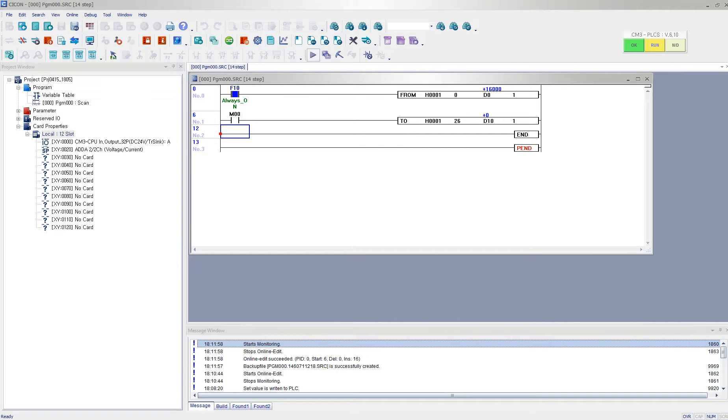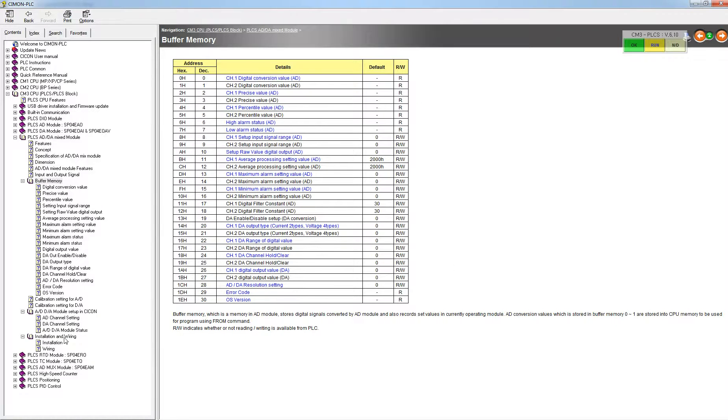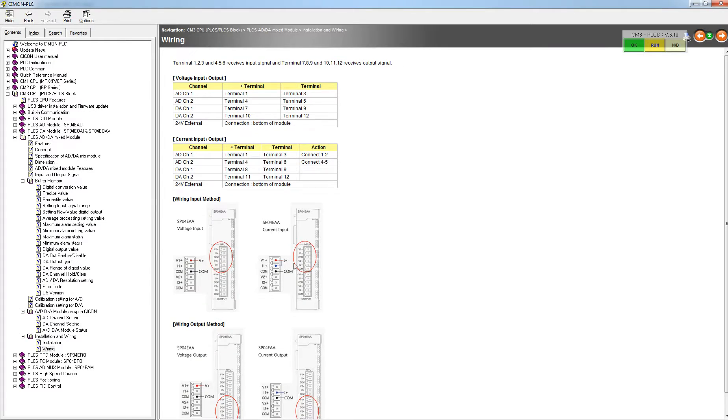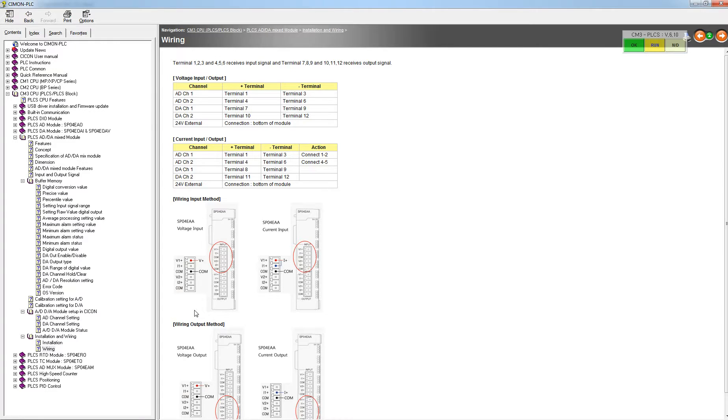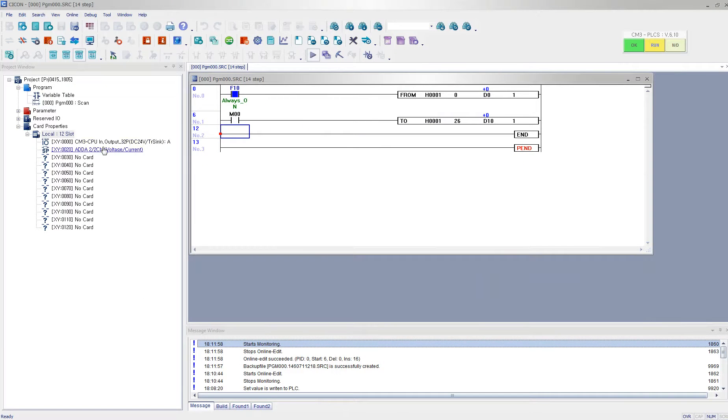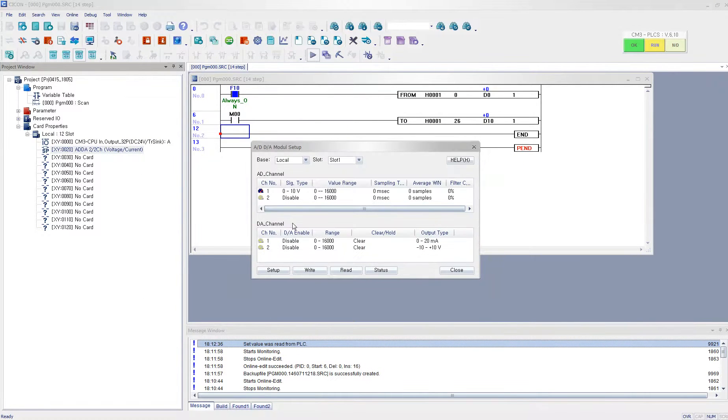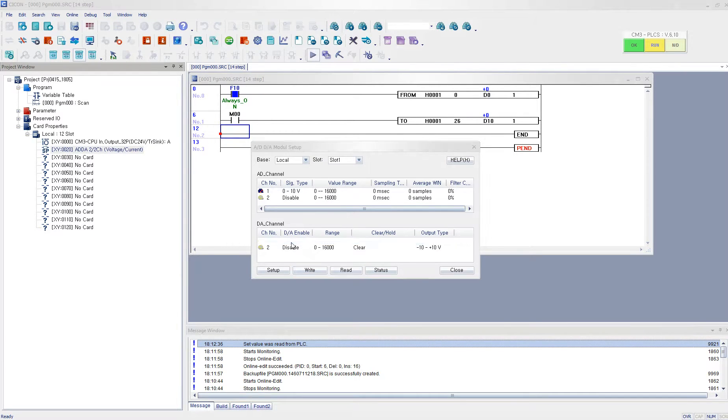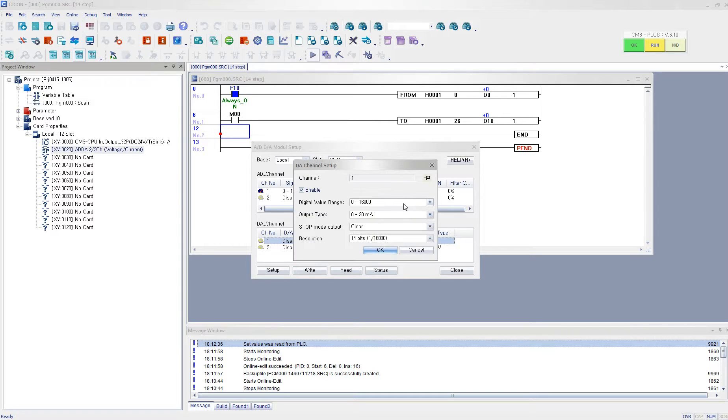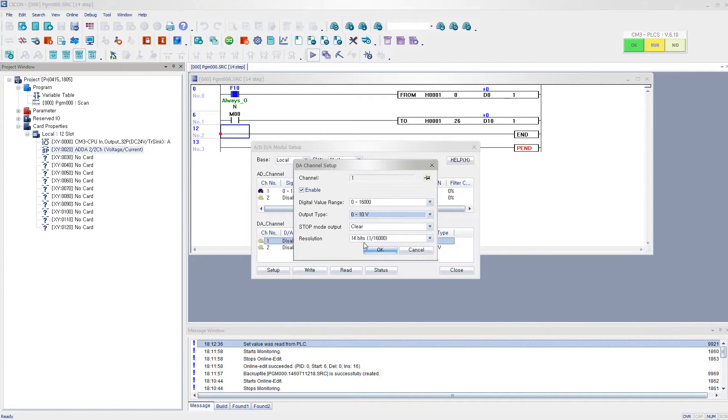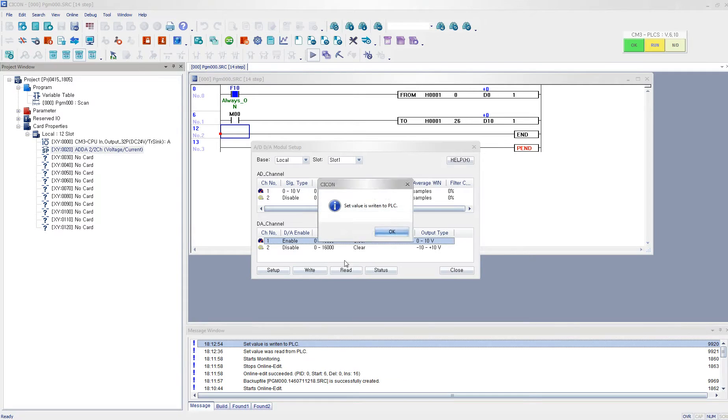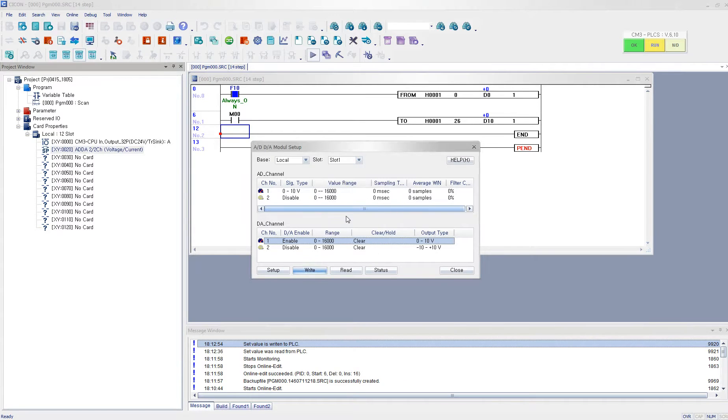And then I forgot to mention that we have to refer to our wiring. For the voltage input, I have wired the voltage here and the COM over here. But since now I'm going to output the voltage, I have to move these wires to the third channel. And then I also need to configure digital value 0 to 10. And then I write it and I click status.